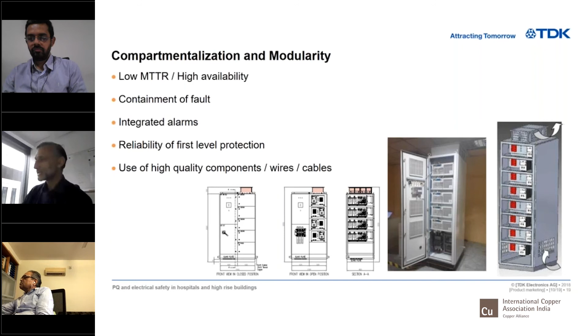Two, the safety concerns in these applications are very different from other installations for PQ devices. Why? You cannot do a simple evacuation. It's very difficult to reach the 80th floor and bring a person down, or reach a ship in the middle of the ocean, or a patient in an ICU on a heart-lung machine. Evacuation is very difficult, meaning prevention is better than cure. Don't have a fire and then rely on fire drills and safety procedures; ensure that the fire itself never originates in the first place.